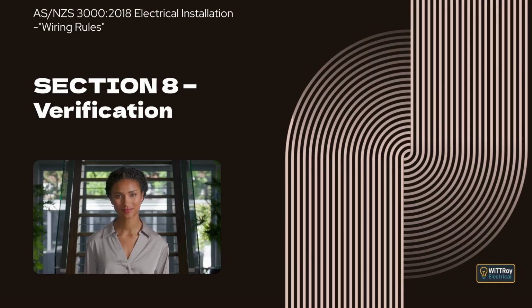Clause 8.3.9.3 Results. This clause explains that the values obtained from EFLI verification must satisfy the requirements of Clause 5.7.4. The requirement is considered satisfied if the measured earth fault loop impedance does not exceed the maximum value for the applicable protective device, or if the measured total resistance of the active and protective earthing conductors does not exceed the maximum value for the applicable circuit protection and required disconnection time. The notes explain how the reference values used for these limits were calculated and the assumptions used for conductor resistance and temperature.